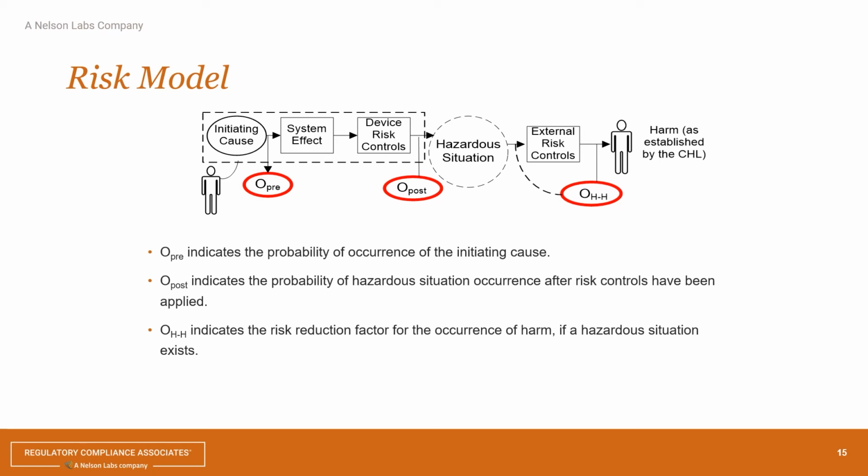And clinically, even though the result is wrong, it's not going to result in any harm to the patient, because the clinician will never do that. The clinician, basically, prevented that harm from happening, although the guideline says if you have a hemoglobin of 8, I need to transfuse you with blood. So that's where that other aspect comes in, and the harm is all the way through, taking all those steps.